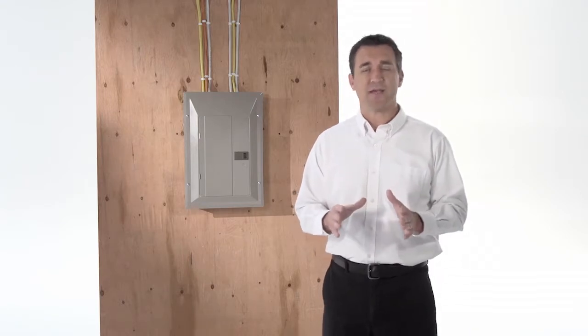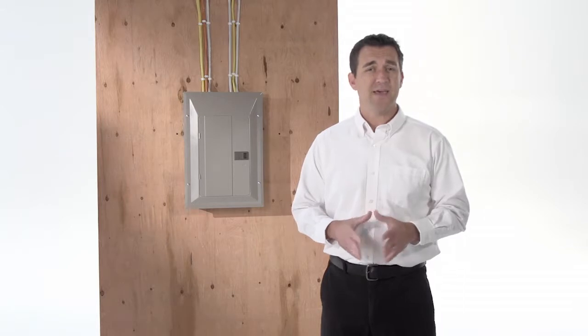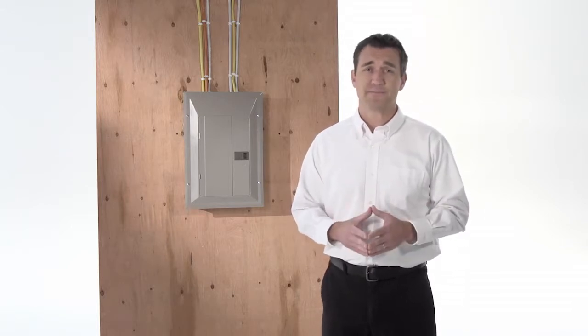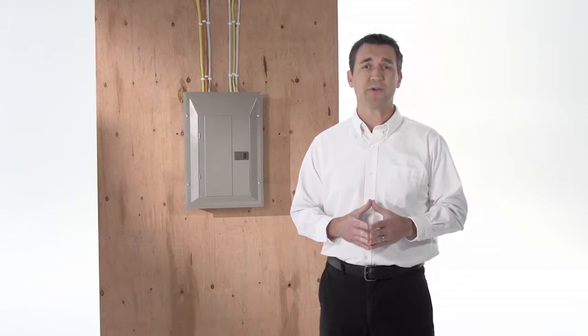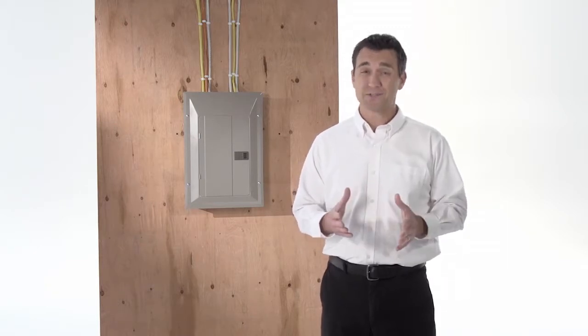Certain electrical panels have lost their certification. It can actually be quite dangerous. These panels can work fine for years. However, as energy demands in typical homes have increased, these panels may overheat and portions of the panel could actually melt.